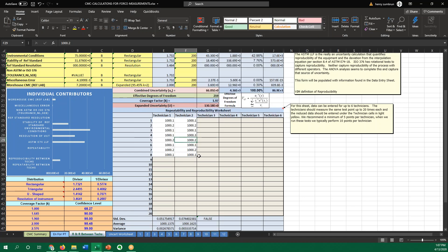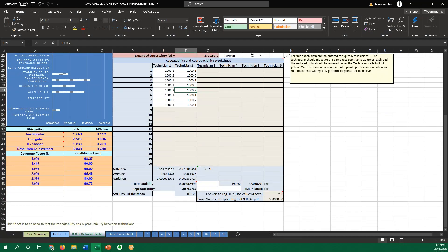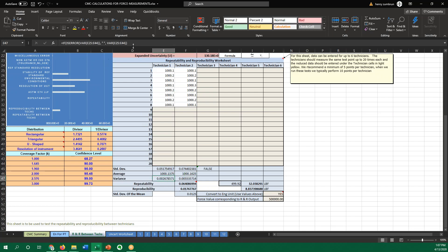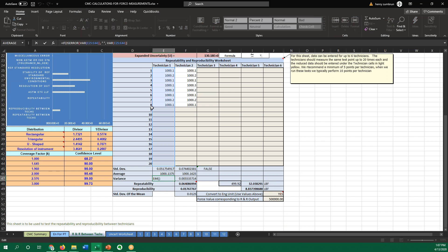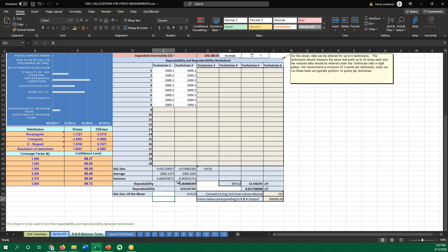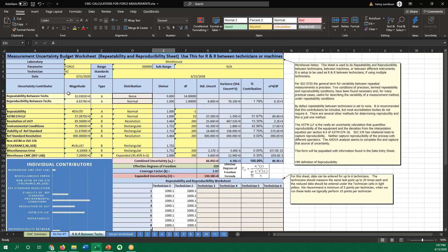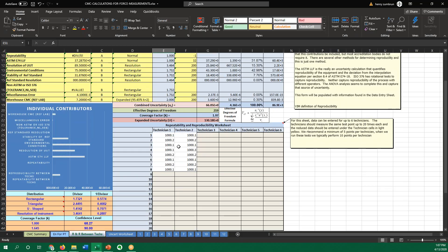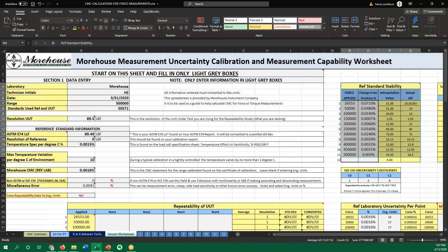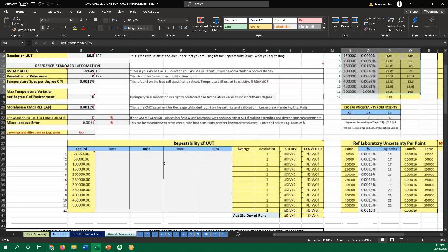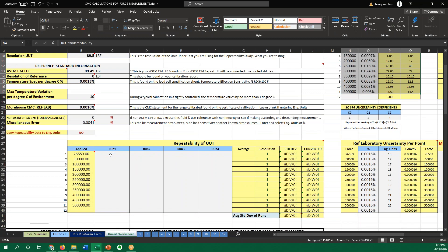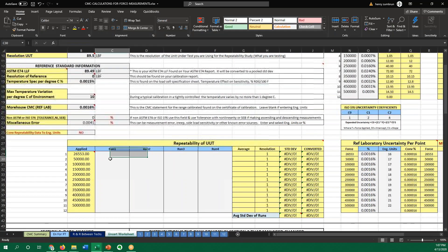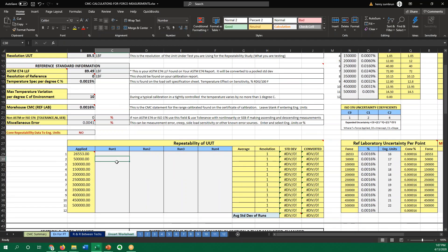And what this one will do, same thing, takes the standard deviation, takes the averages, also takes the variance of all these points. And it's going to give you the repeatability and reproducibility numbers between groups. So if you want to figure out repeatability and reproducibility between techs, this sheet will do it. But also on this sheet, you might get repeatability because you're dealing with more than just the range.